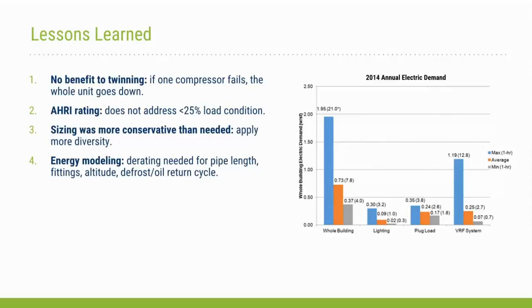Our sizing in retrospect was more conservative than needed in terms of applying some of GSA's standard guidelines for process load. This building ended up being a heavily process load managed building, operating down as low as 0.1 watts per square foot at night and about 0.2 during the day. And so there was the ability to potentially apply more diversity in the design sizing.